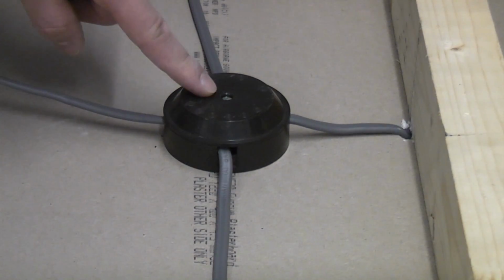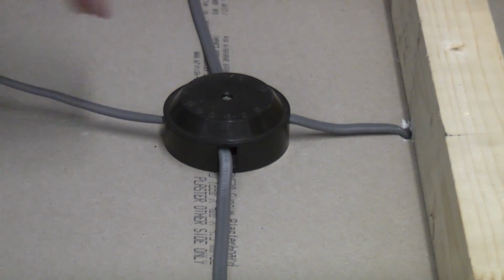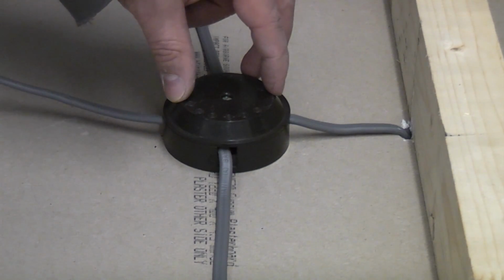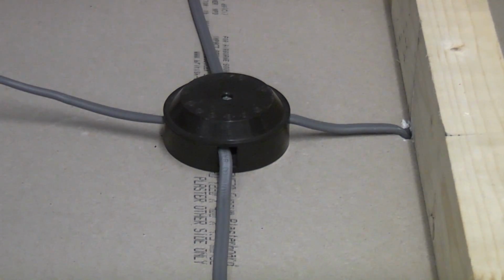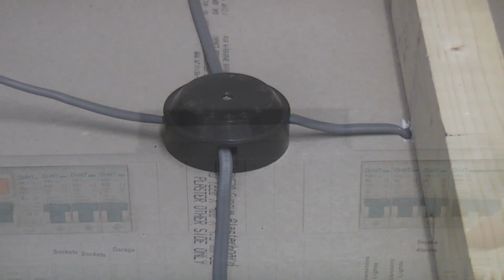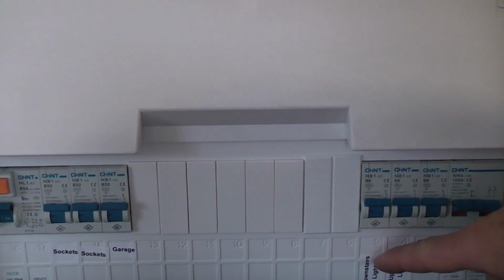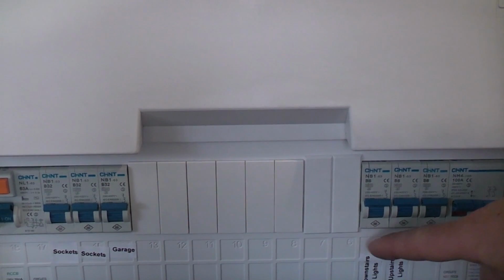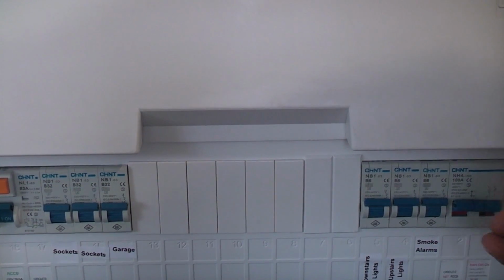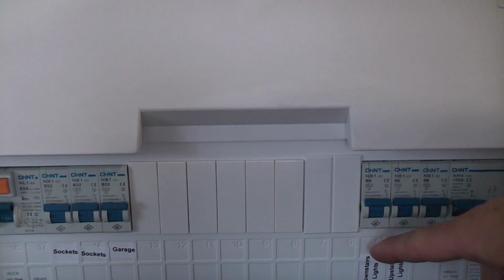We've now located the ceiling rose and we're going to take a supply from this to go to the FCU. Before we do that, we need to go and isolate the electric. So this is the consumer unit and you can see that the downstairs lights are clearly identified, but you should never take it for granted that that switch isolates all the downstairs lighting circuit. You always need to check.